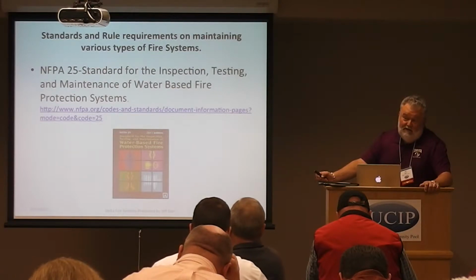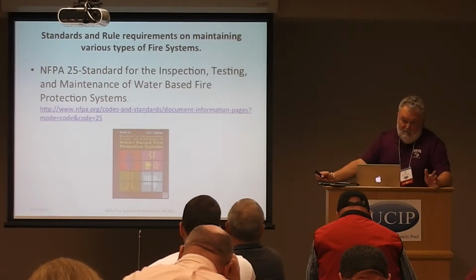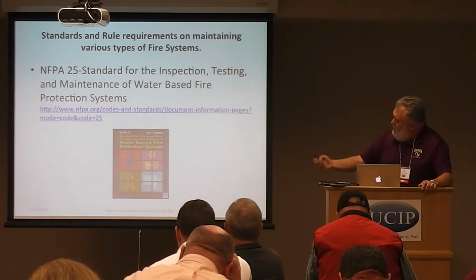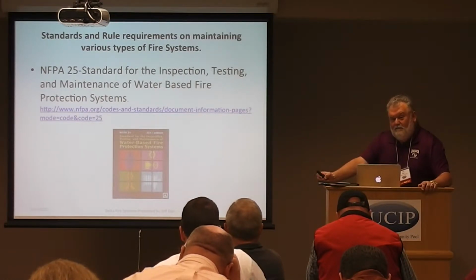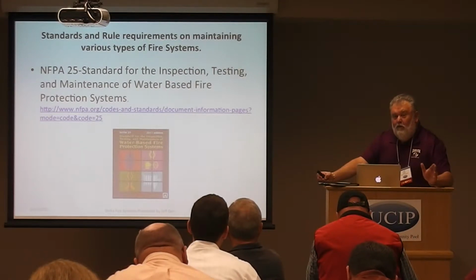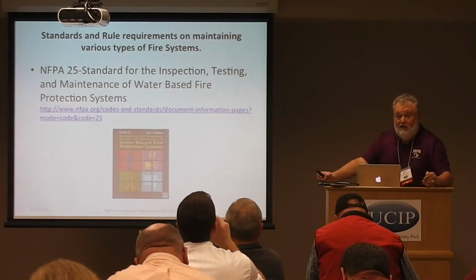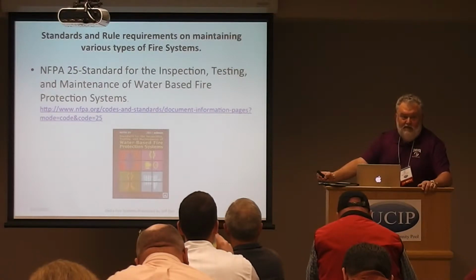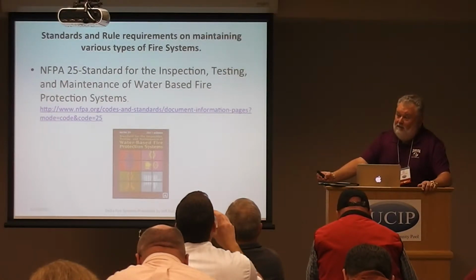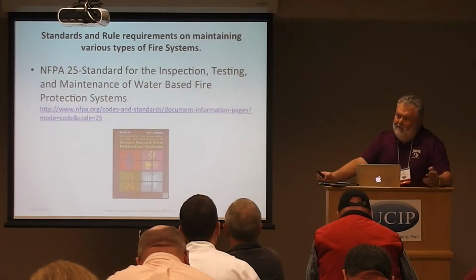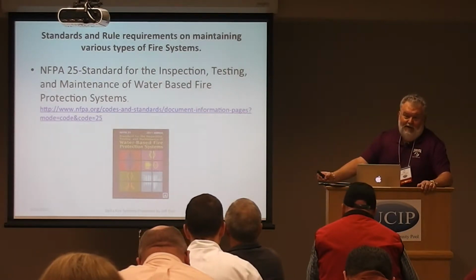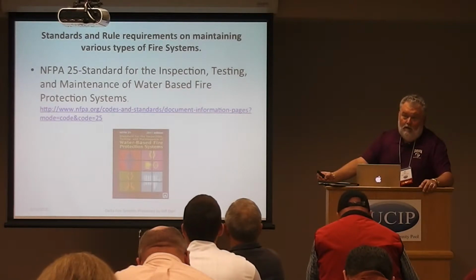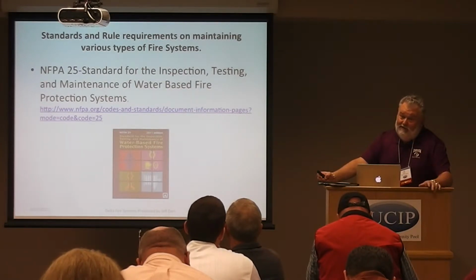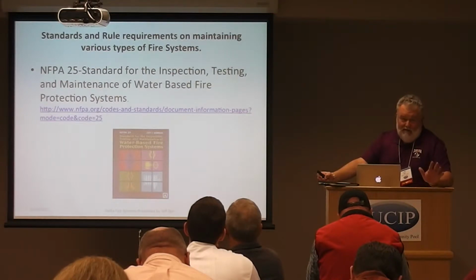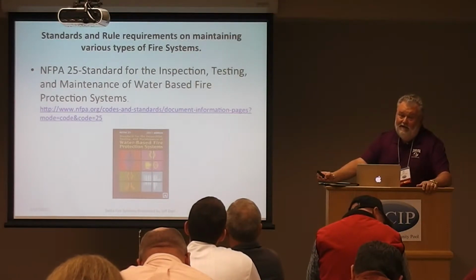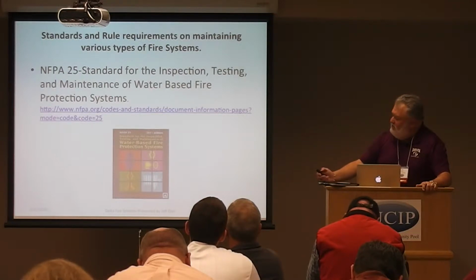We could be inspecting a system that was installed in the 80s, 90s, still inspect by the NFPA 25 for 2011, but you don't have to bring it up to any code standards because the assumption by 25 is it was accepted, at the time it was installed, so it was correct. A lot of inspectors sometimes will try and say, well, you're too far off a wall with this head or something like that. That's really not the intent of the inspection part. You have to assume, unless that wall was added later, that system was correct when it was installed.